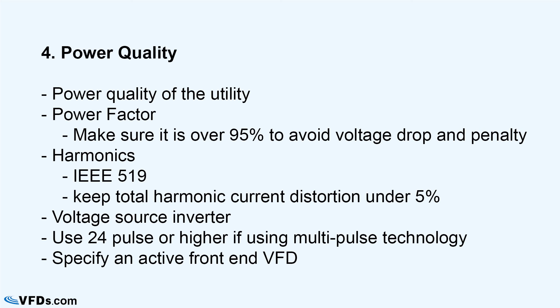Be careful with current source inverters — they can have terrible harmonics and need filters. We recommend a voltage source inverter and either a multi-pulse technology of 24 pulses or higher (18 pulses is marginal, under 18 pulses is not acceptable), or specify an active front end on your variable frequency drive.